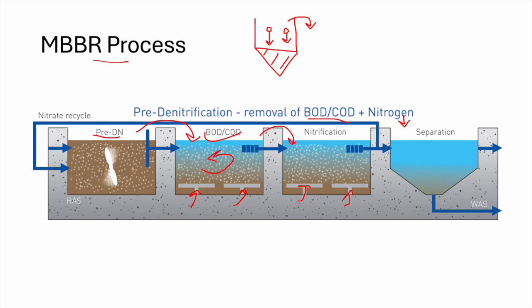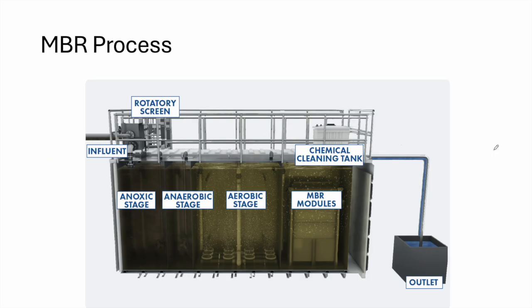By these two stages — pre-denitrification and nitrification — we are able to highly reduce nitrogen. At the end, we have a secondary settling tank where particles settle by gravity, forming activated sludge that is wasted. There is no need to return the sludge. At the end of this process, we will have excellent effluent quality.